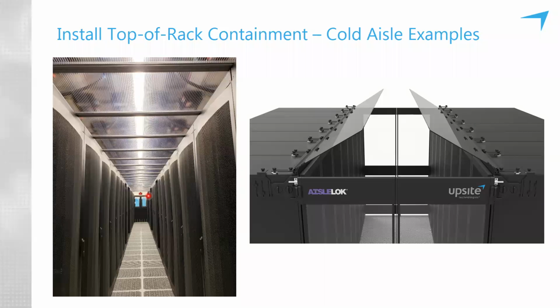But nonetheless, the cold aisle, these are panels. Think of a picture frame. So you've got an aluminum frame with an insert there with some special material that shrinks. It doesn't melt. It kind of deforms and falls out of the frame when it reaches about 135 degrees. And that's before the temperature of a sprinkler head might go off above it.